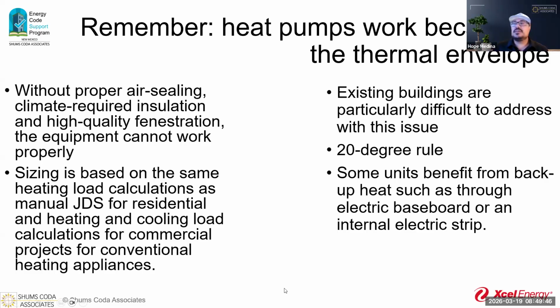Sizing goes through the same process—that was a great point. A different question is whether we treat heat pumps differently because they're more efficient, say 300% efficient—does sizing still matter? Yes, we still want it sized for the loads appropriately, because if it's not, we get bad outcomes: incorrectly sized equipment for the BTUs that particular house or building needs.